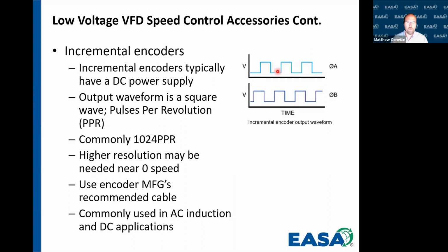So you're looking at these different pulses, and the encoder actually gives you so many pulses per revolution, or PPR. Most commonly, we're going to see 1,024 of these pulses per revolution. A lot of encoders come with a 1024 PPR. The closer we're going to be towards zero speed, and we need to maintain zero speed or torque at near zero speed, a 1024 PPR encoder might actually not be enough. We may need one that pulses 2,048 times or 4,096 times per revolution, so that we have a better understanding of the position of the rotor near zero speed.